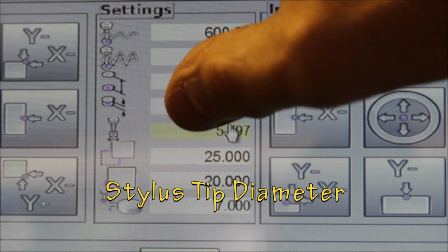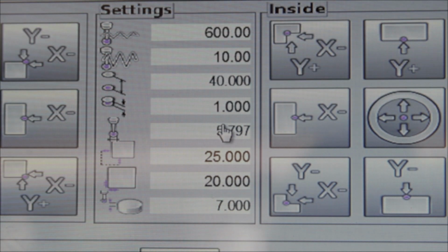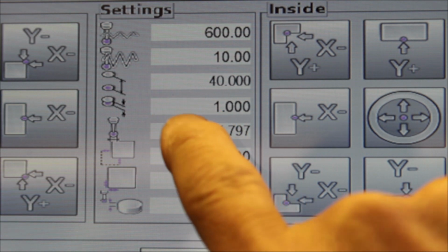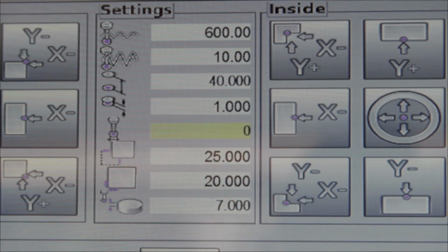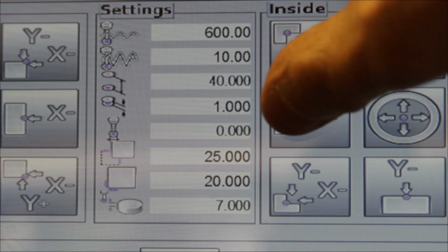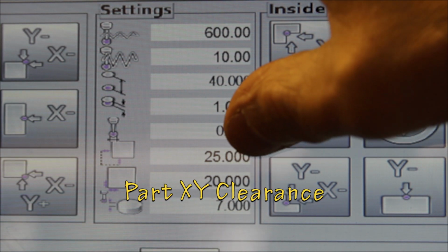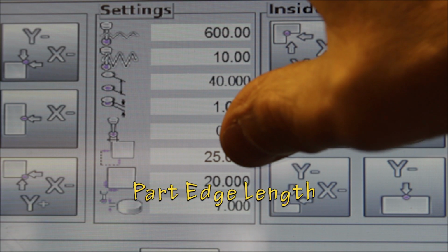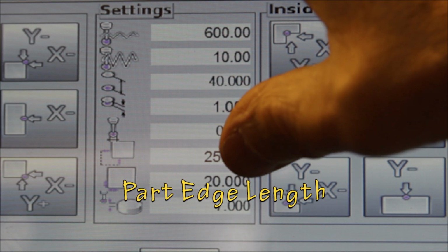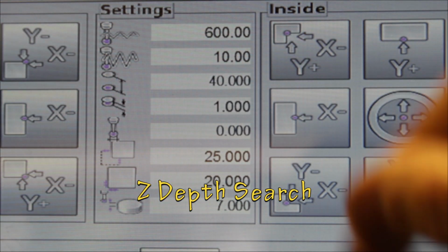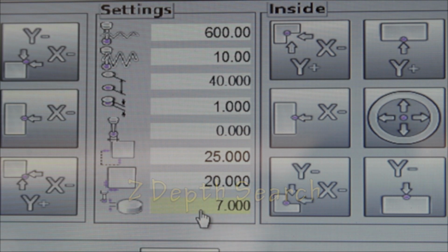This is the effective probe diameter, and I've been fiddling with this, so what we're going to do is set that to 0. Oops. If I can get that, 0, enter. Then you've got a couple of clearance distances: the clearance distance from the edge, and the offset from a corner or a radius. The last one is how far down it pushes the probe to do a search. So in this case we want that as 0.